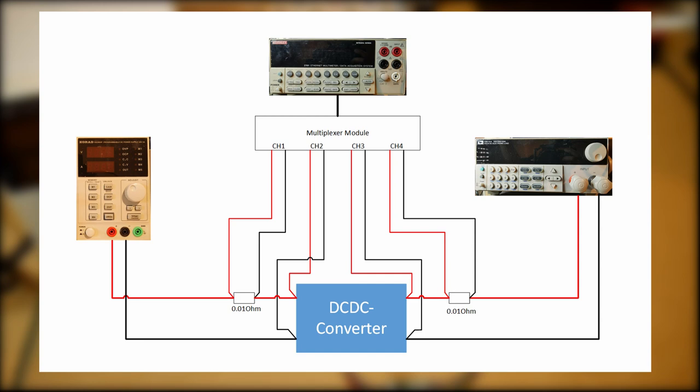I want to measure the input and output voltages as close to the pads of the tested module as possible. That's why I need to connect two cables to each pad: one to carry the current and one to tap off the voltage.